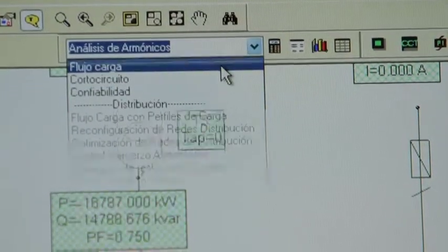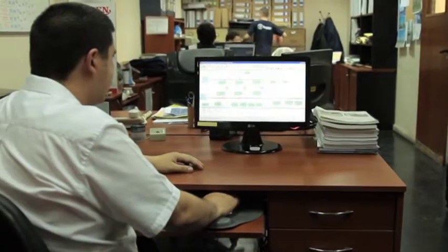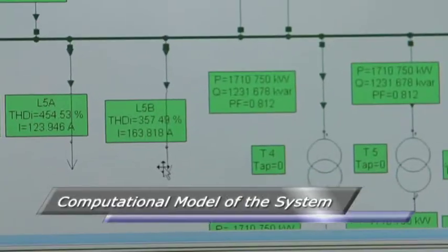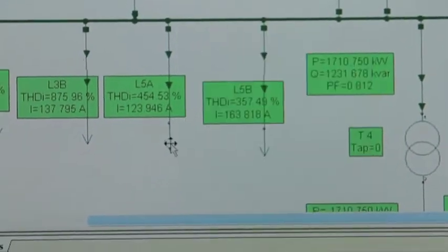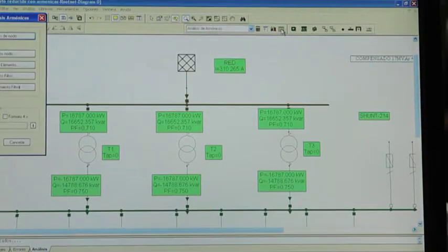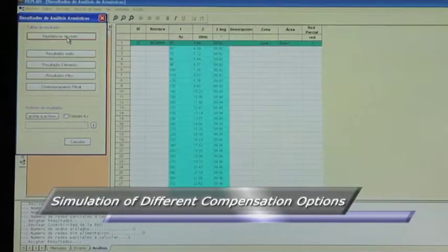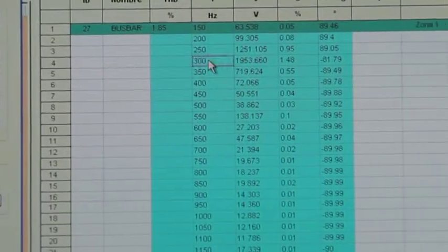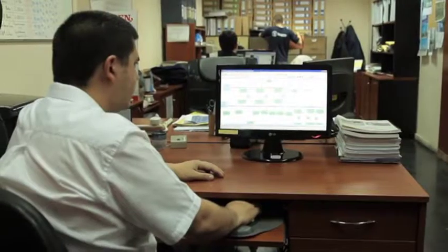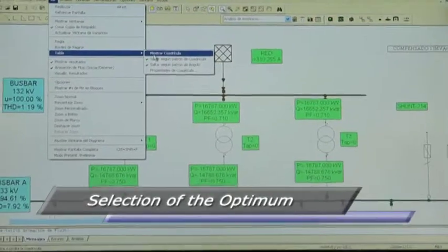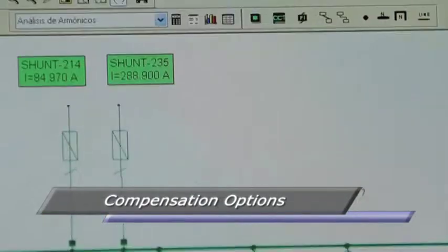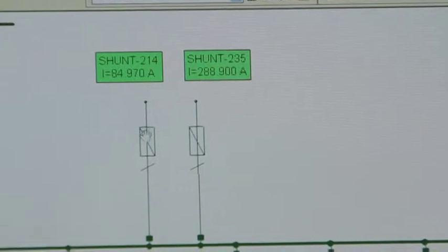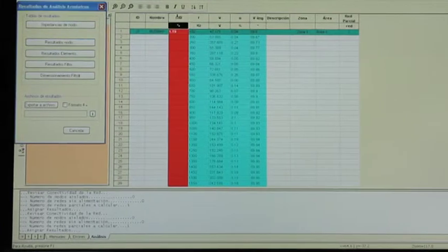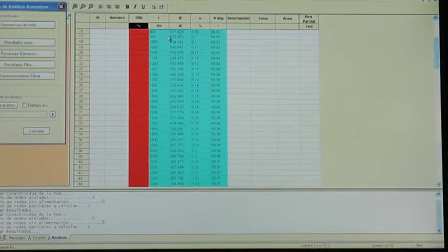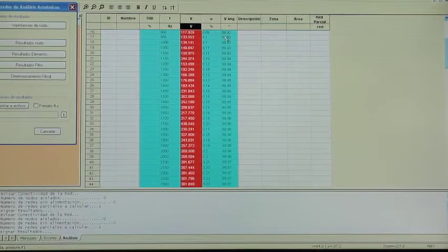The next stage consisted in developing a computational model of Wafra's distribution system, based on a powerful simulation software package. Once the computational model was fine-tuned, current and forecasted load scenarios were selected for each of the medium voltage feeders. The optimum size, MVAR grading, and location of harmonic filters were chosen by using those configurations which minimize voltage drop and losses, gave power factor values closer to unity, avoided overcompensation, and reduced THD to acceptable values.